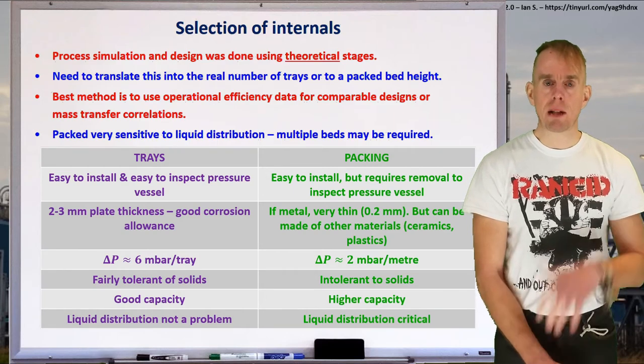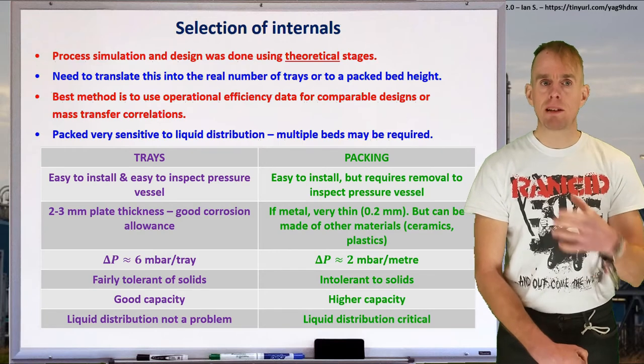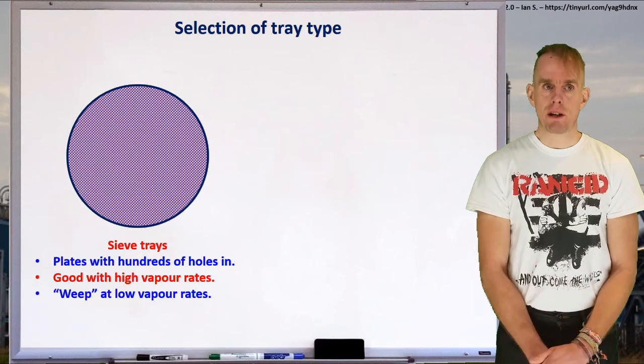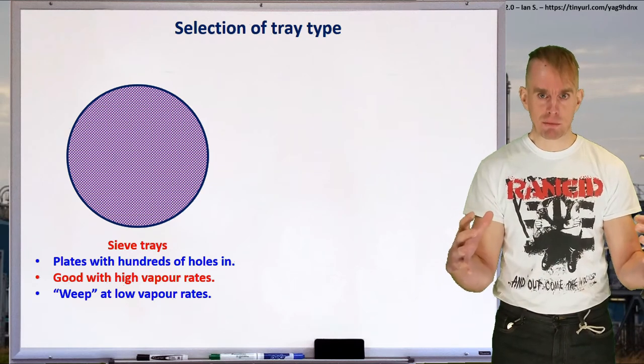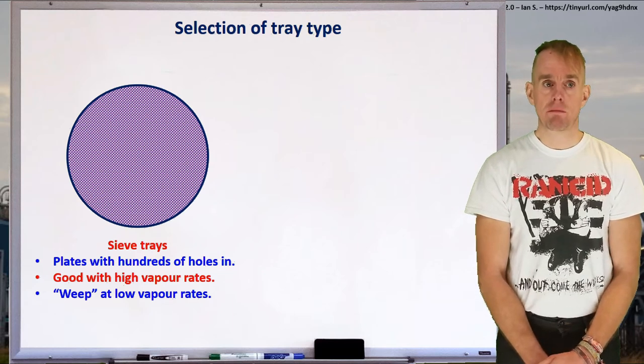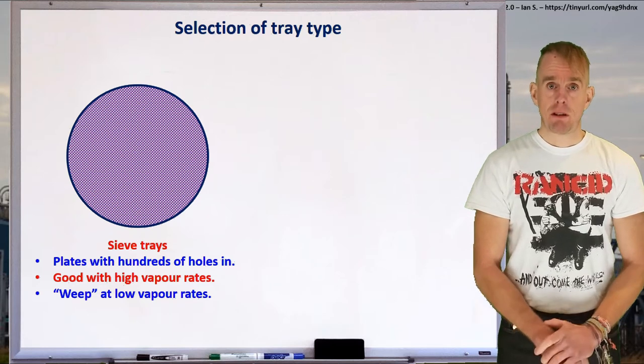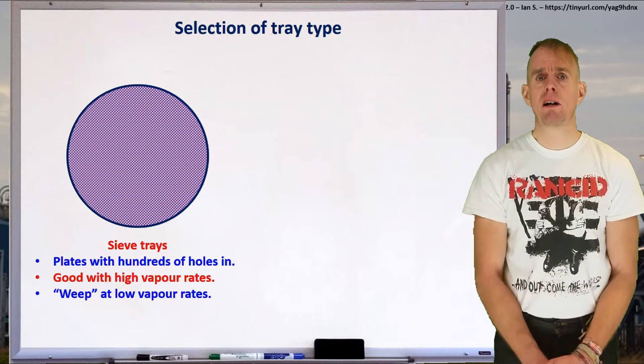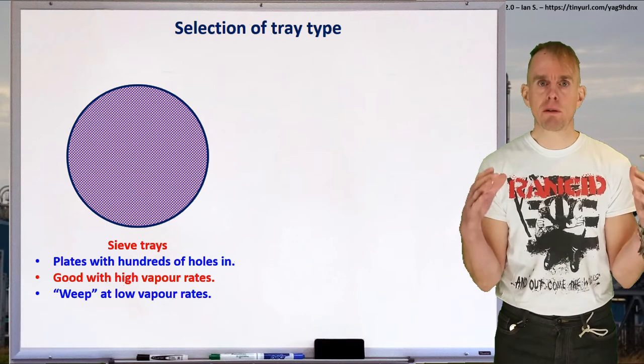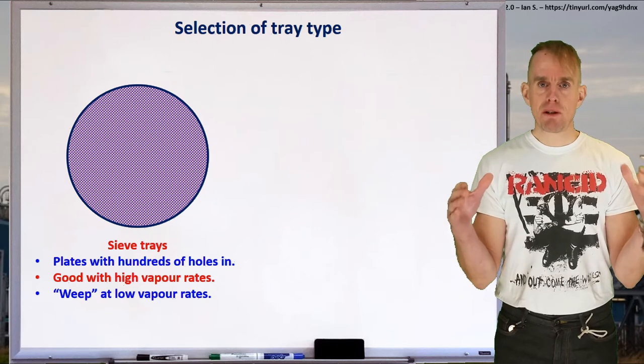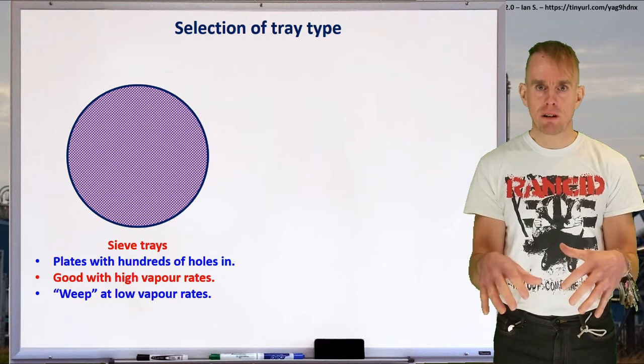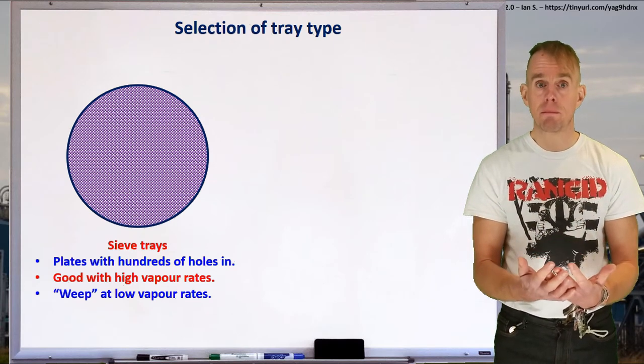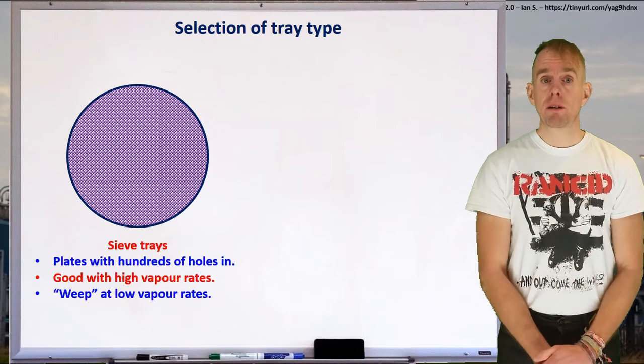Let's look at tray systems first, starting with a few things around tray design and configuration. The simplest distillation tray is a sieve tray — essentially a circular piece of material with a chord cut along it and thousands of holes drilled in it. Sieve trays are cheap and typically won't go wrong — there's nothing to break unless it falls to pieces through corrosion. They will only work well at high vapor rates because on the tray there is a reservoir of liquid held back by a weir, and you need high vapor flow through those holes to prevent the liquid from weeping.